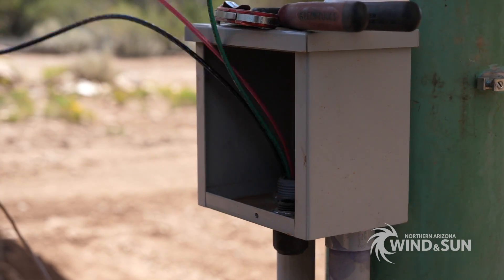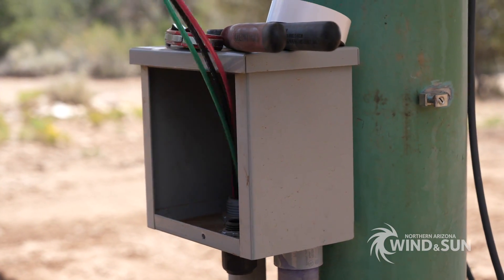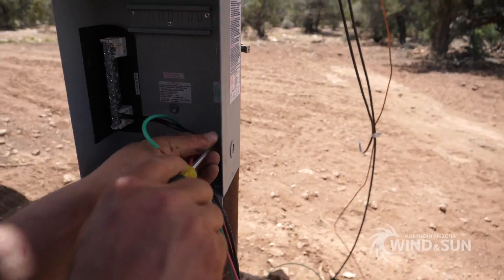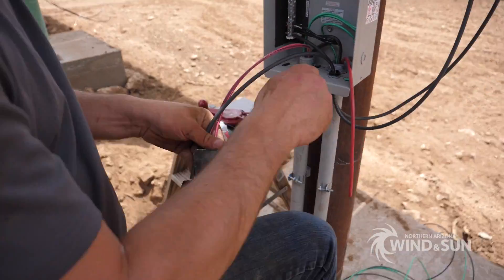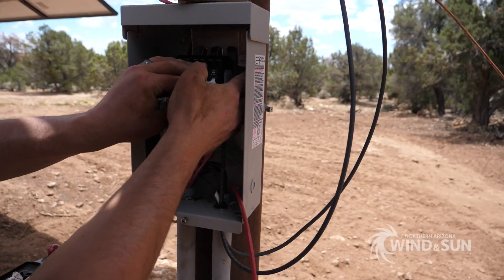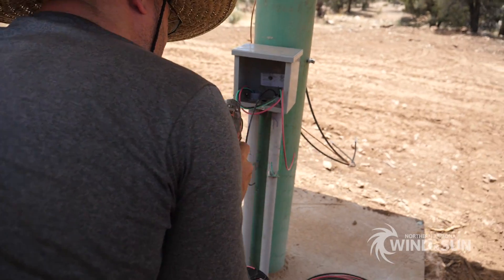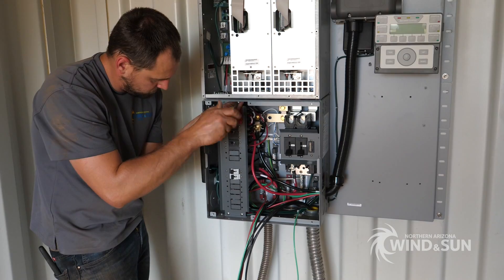Solar panel wires and grounds were connected into a combiner box. This joins each group of six series-connected panels together in parallel before going back to the charge controller. A ground lug was installed on each individual solar panel frame. These ultimately tie back into the UFER grounds that are within the concrete foundations.